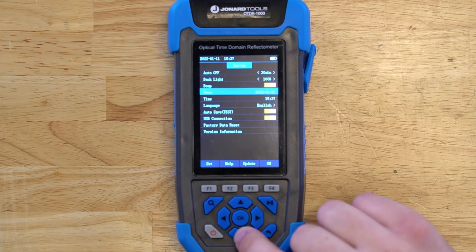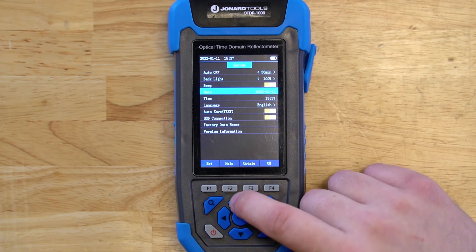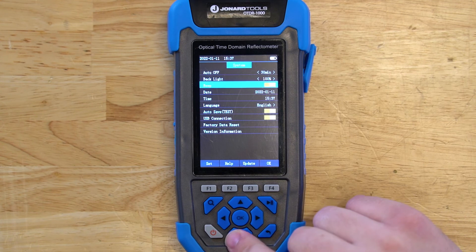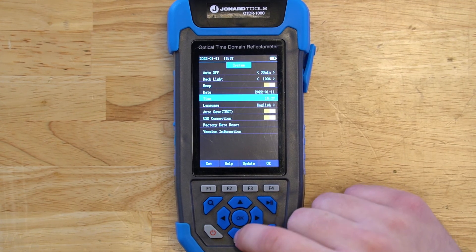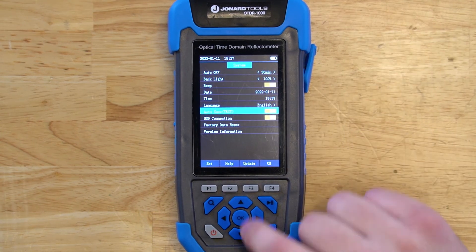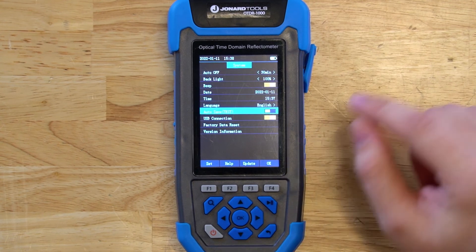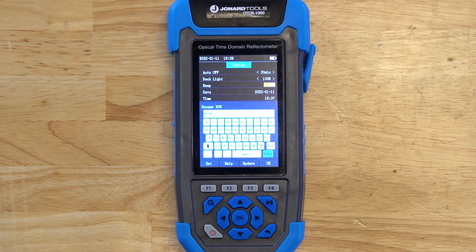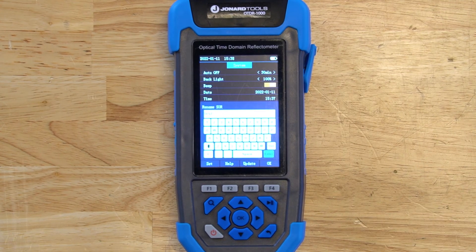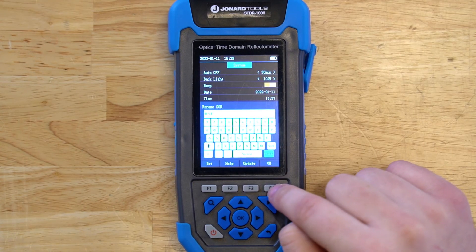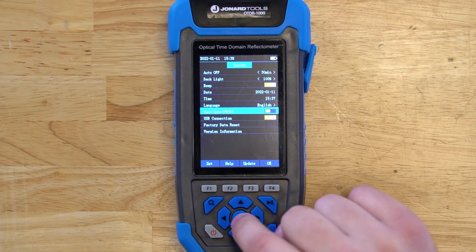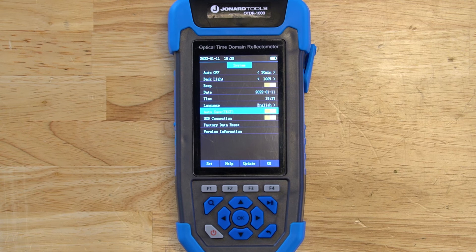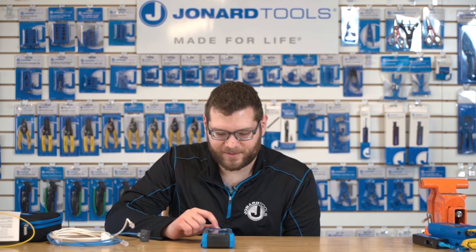You can also turn on the beep, which adds an audible beep whenever you navigate the menus of the OTDR-1000. There are also date, time, and language settings that can be adjusted. There's also a great autosave function for the OTDR module — you can set a file name such as 'test,' and every time you run a test, it'll generate files named test one, test two, test three, etc., saved in individual folders for each day. This way you don't have to manually save every time, which saves a lot of time.